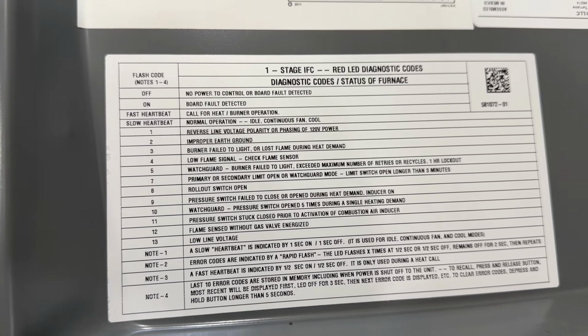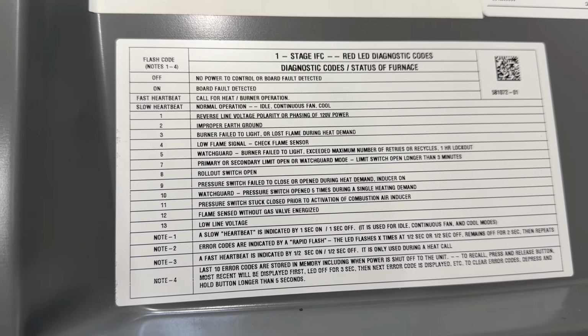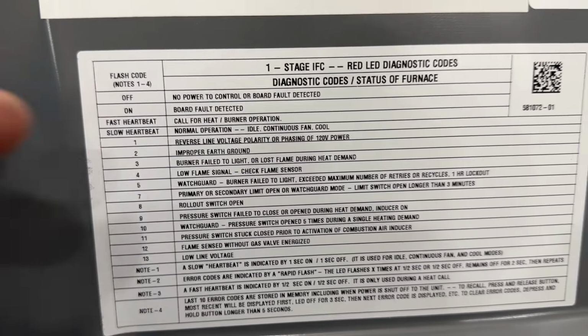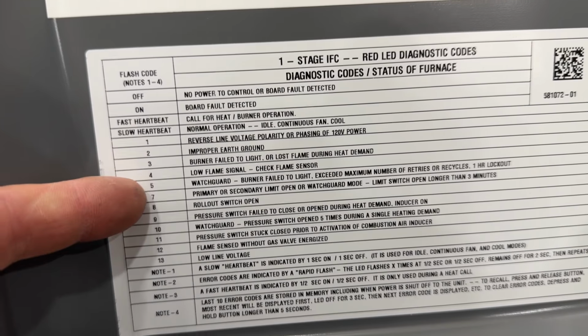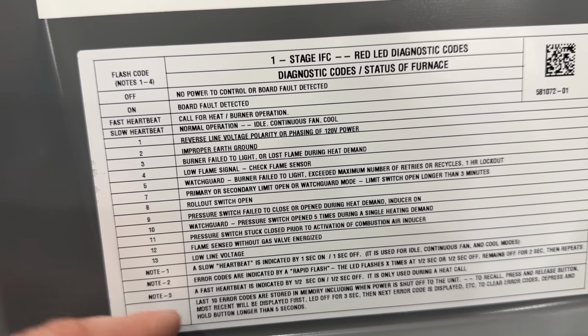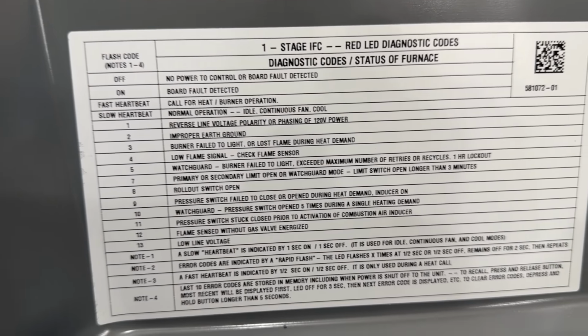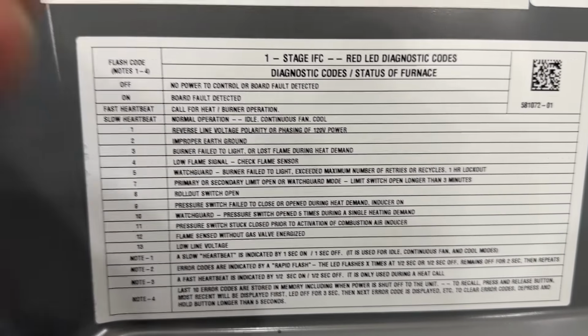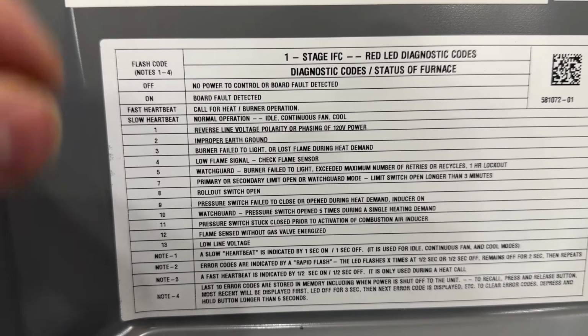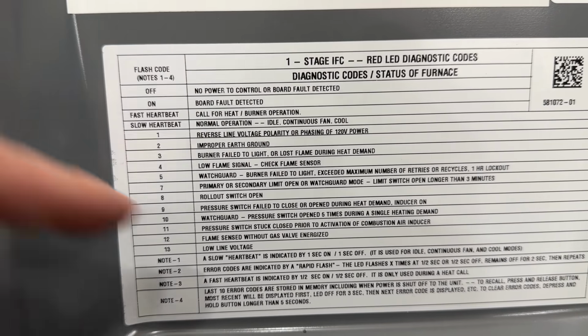And then every single furnace is going to have this right here. This is for your diagnostic codes. So it tells you, based on how many flashes that LED is flashing, it will give you a good idea as to what's going on with that furnace. Now, this is not directly going to tell you what's wrong. There could be multiple issues based on what code it is, but it'll tell you generally where to look.